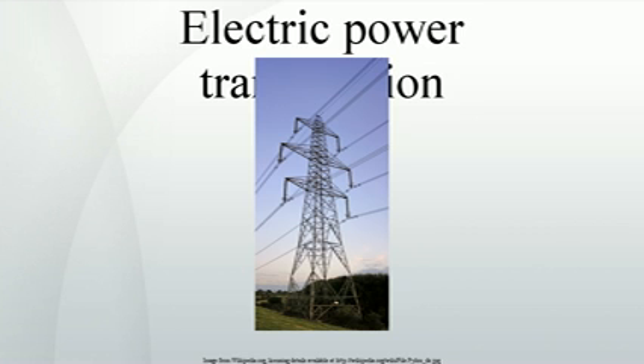The transmission system usually does not have a large buffering capability to match the loads with the generation. Thus generation has to be kept matched to the load, to prevent overloading failures of the generation equipment. Multiple sources and loads can be connected to the transmission system and they must be controlled to provide orderly transfer of power. In centralized power generation, only local control of generation is necessary, and it involves synchronization of the generation units, to prevent large transients and overload conditions.